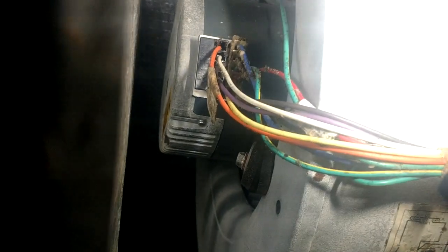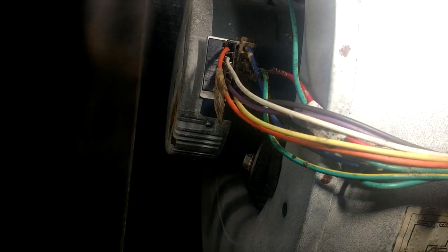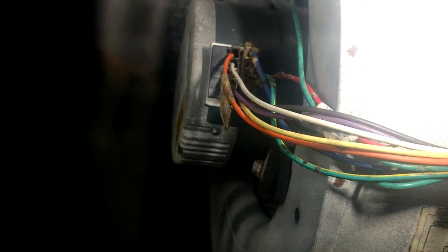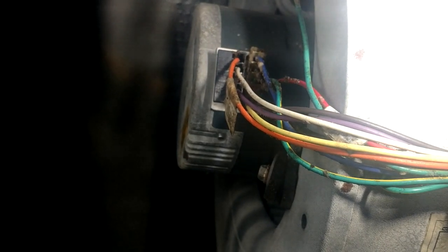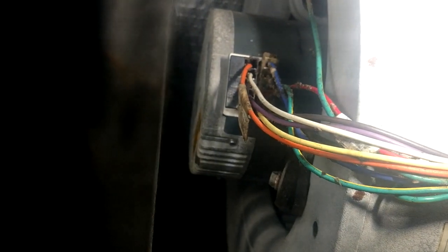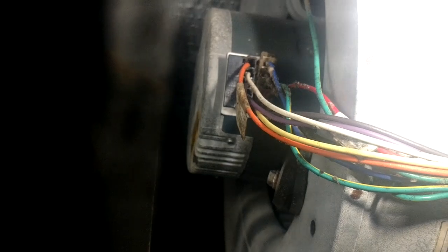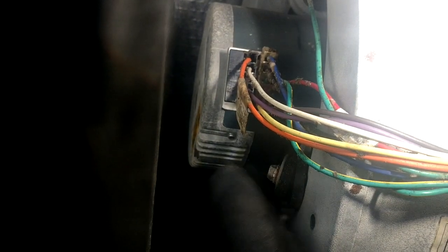So now I've got to get my meter down inside of there and check our high voltage to make sure that the high voltage is present. And if it is present on there, then this is going to turn out to be a bad motor, because we've got our 24 down there telling it to come on. So if we also have high voltage over here, then we're going to be looking at replacing that X13. So give me just a second, we'll get our leads in there, see what we got.